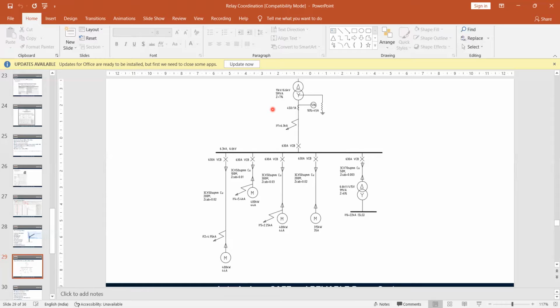Okay, so my CT was 500. So that divided by the 110% of that load current of the feeder. Okay. So it's 262 times 1.1, or we got 288 divided by 500, you got 0.576.